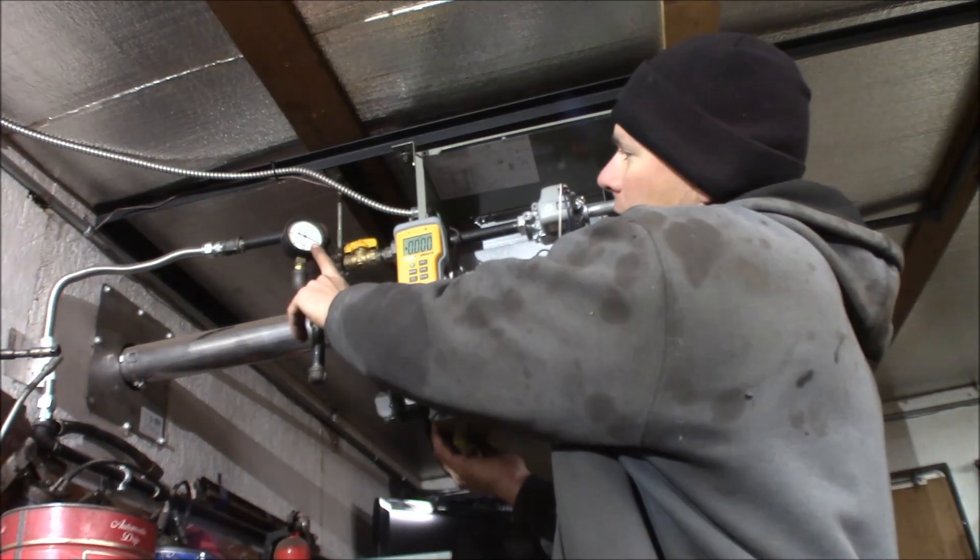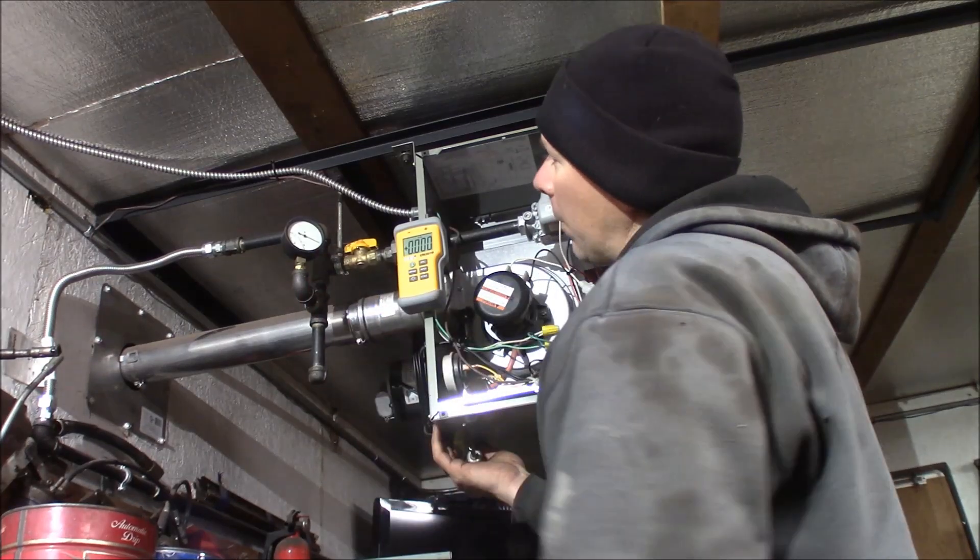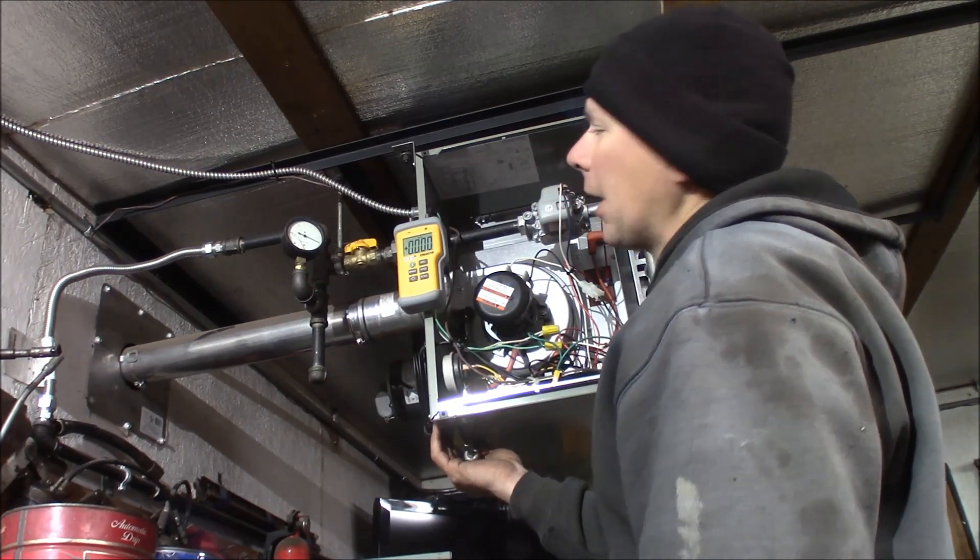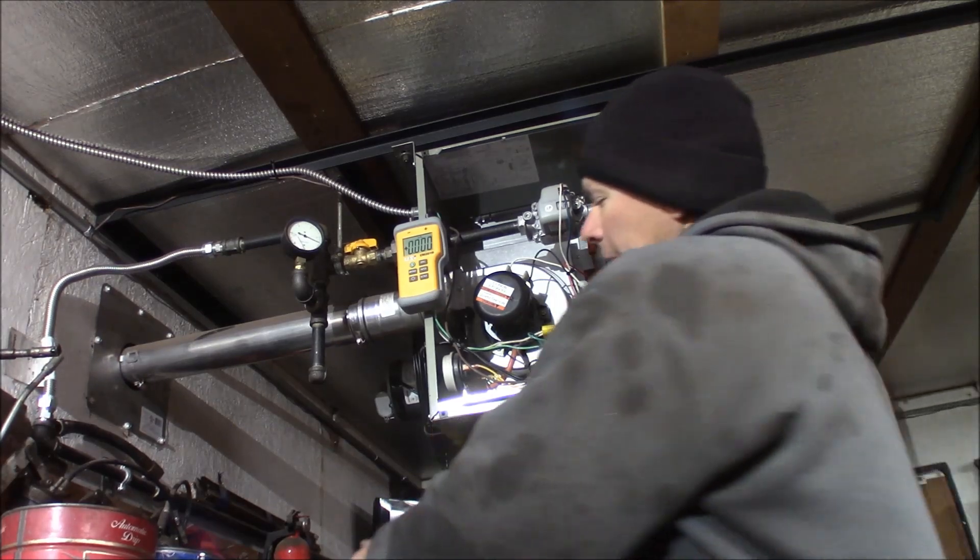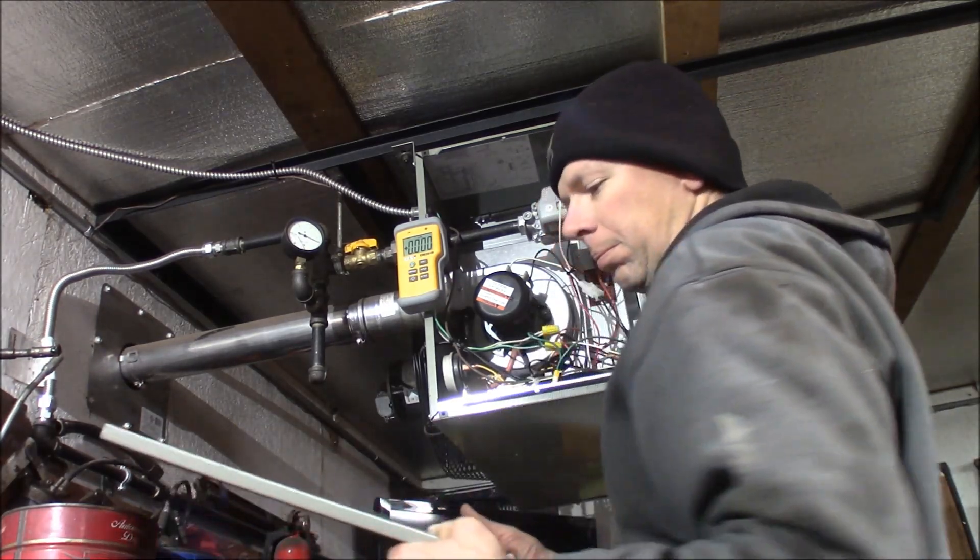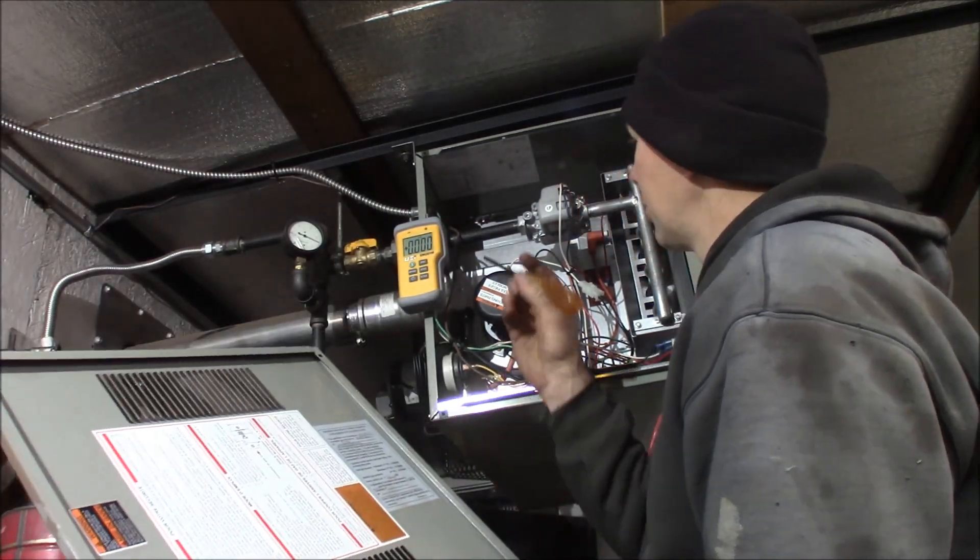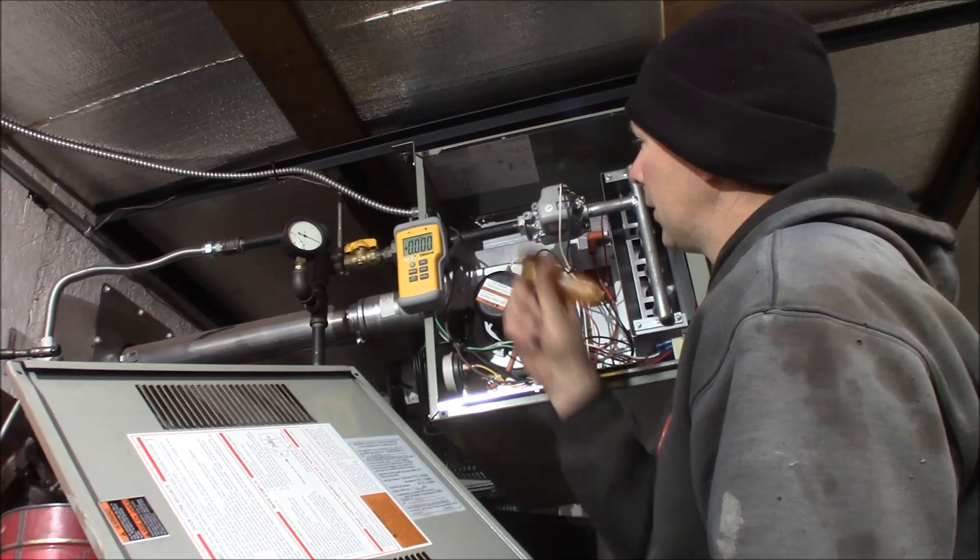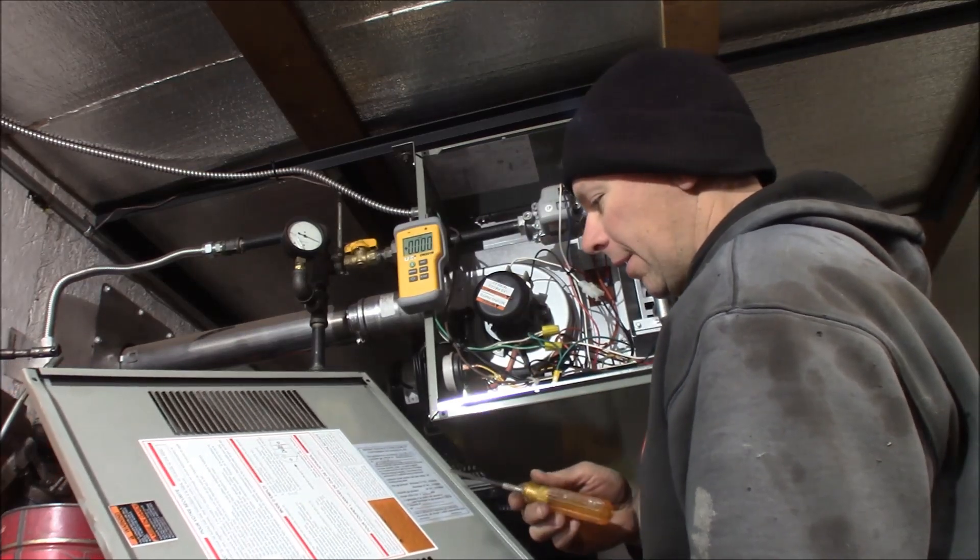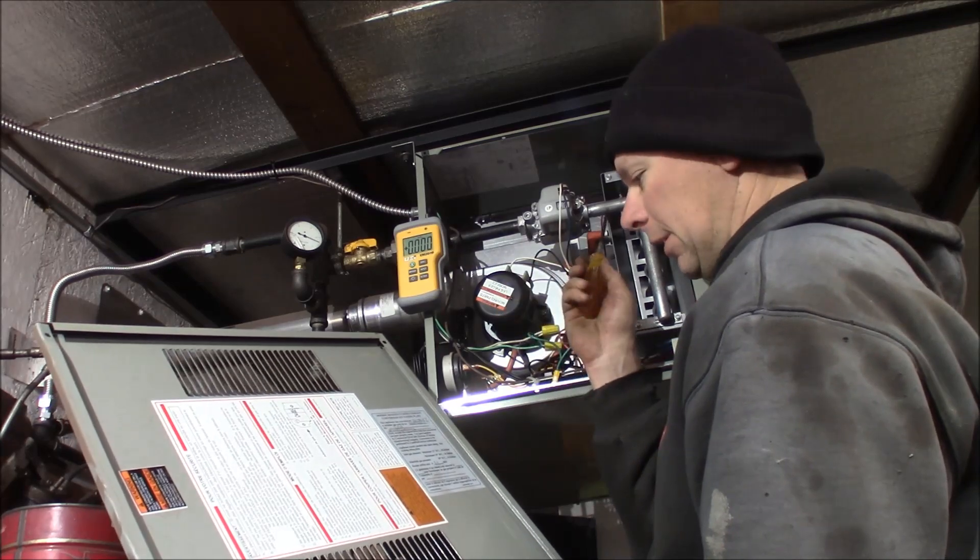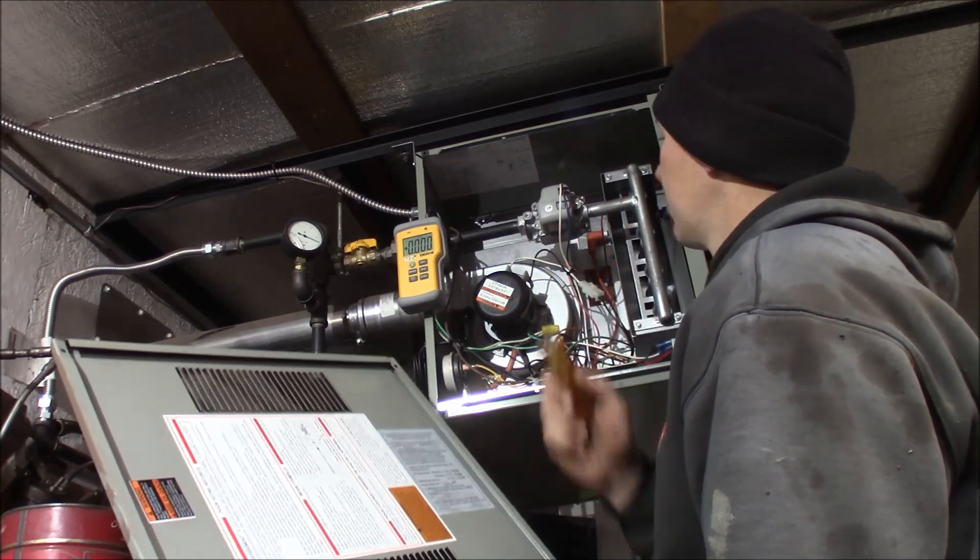But I have a gauge which right now is showing about 13 and a quarter, 13 and a half inches of water column. I've got my booklet here for this heater on propane. They want a minimum of 12 inches of water column here at the manifold and a maximum of 14, and then they want 10 here on the manifold side.